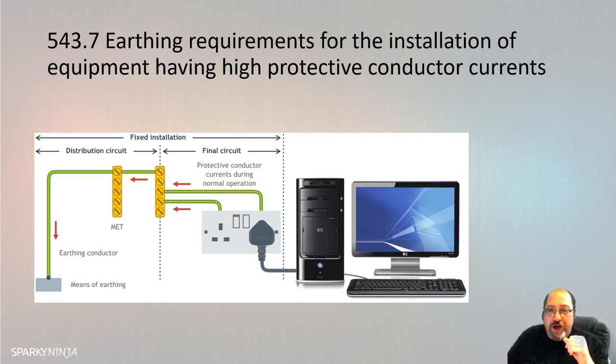We do need to understand that that goes all the way to the fuse board as well. So in the case of a circuit of high integrity earthing, we'd have to have the protective conductors in two terminals. Now, if you remember in section 514, there was a label for this purpose. There was a label that warned electricians that circuits 7 and 9 or 7 and 8 or whatever are both circuits of high integrity earthing, and maybe they are sharing the protective conductors, or maybe this terminal does the protective conductors of 2 and this protective terminal does the other 2. But they must be separate for the circuit concerned.